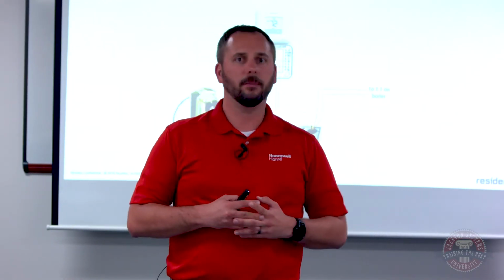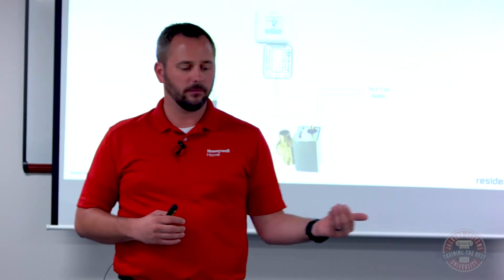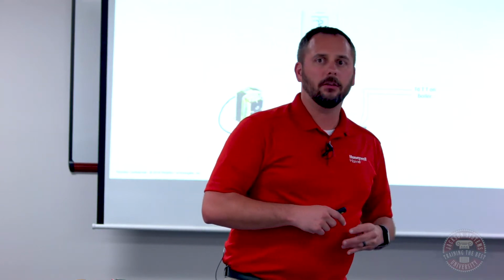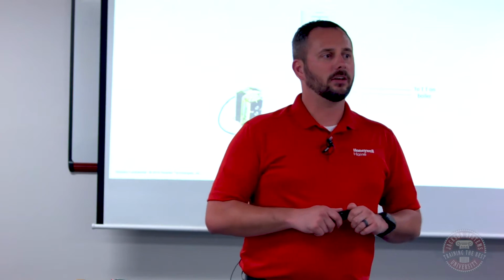So in our system, we at Resideo and Honeywell Home sell a lot of transformers. If you wanted to hook up a simple system with a transformer, this is essentially how you would do it. You're going to come from the transformer, and I'll give you a hint on some of the wiring if you haven't seen some of this. You have R and C on a transformer. When you're wiring up a thermostat, you typically take the R from the transformer to the R on the thermostat. It's basically the load side of that transformer. And we talked about it being a switch.